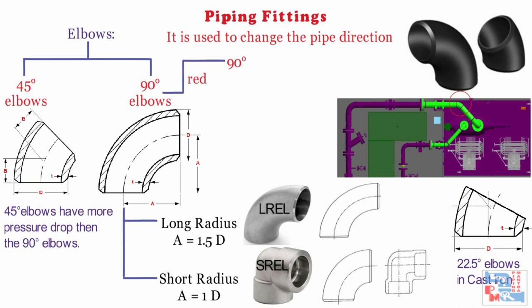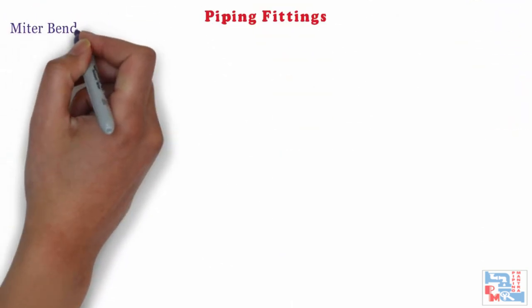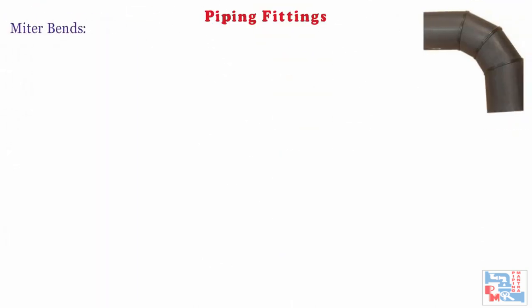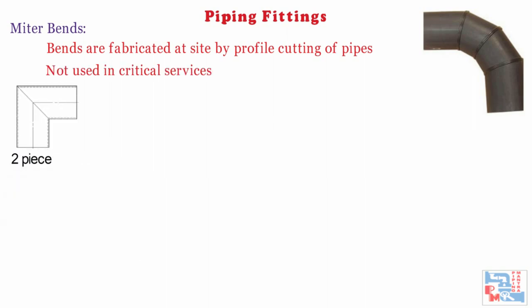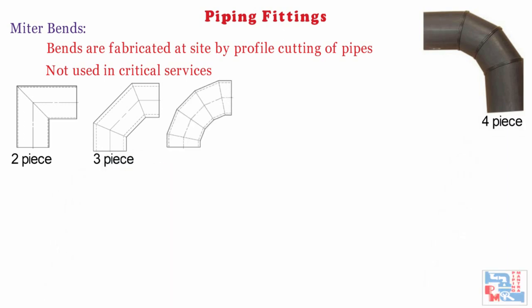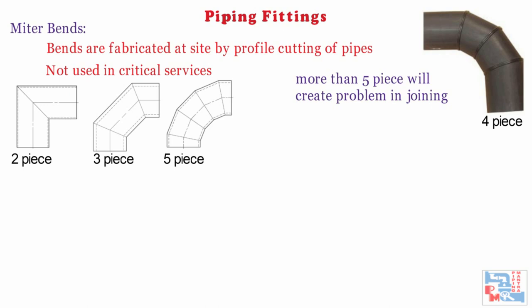We also have 90-degree reducing elbows, used to change direction and pipe size simultaneously. Miter bends: any bend with more than 1.5D bending radius has to be made as per requirement. For large diameter piping, bends are fabricated by profile cutting of pipes and are called miter bends. These are normally not used in critical services. Miter bends with 2-piece, 3-piece, 4-piece, or 5-piece construction can be made — it should not exceed 5-piece, as more joints will create problems. Like elbows, we also have 90-degree and 45-degree miter bends.